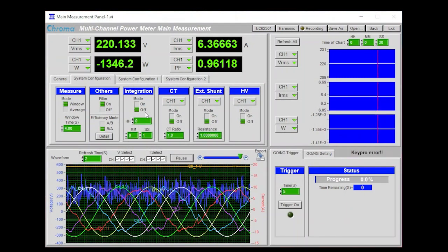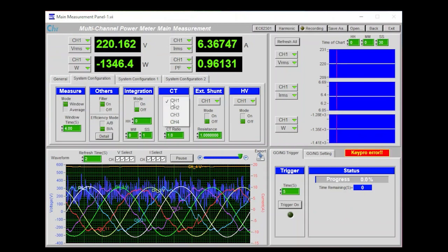We can also set the integration time required. We can set the CT mode and its ratio. We can set the external shunt mode and its resistance, and we can set the high voltage mode. We can do this for each channel.